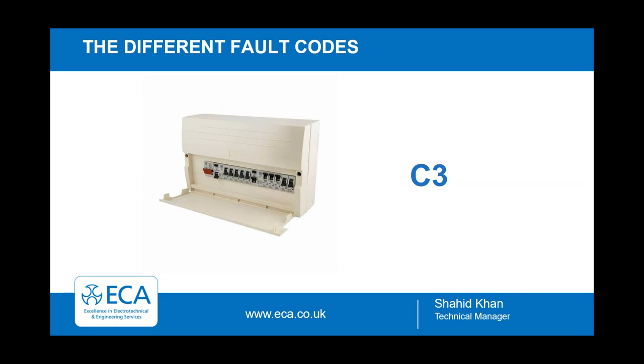So the periodic inspection notice and RCD functional test button notice are not there, and the circuit schedule is missing as well. Also, what's it made out of? It's made out of a combustible material, i.e. plastic. Another C3.